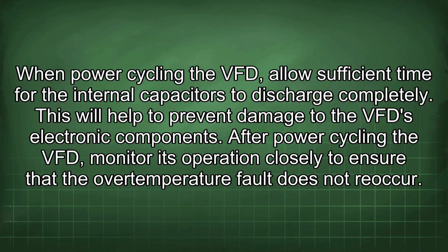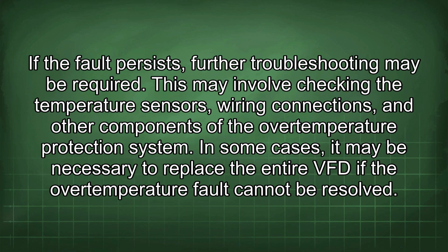When power cycling the VFD, allow sufficient time for the internal capacitors to discharge completely. This will help to prevent damage to the VFD electronic components. After power cycling the VFD, monitor its operation closely to ensure that the overtemperature fault does not recur. If the fault persists, further troubleshooting may be required. This may involve checking the temperature sensors, wiring connections, and other components of the overtemperature protection system.